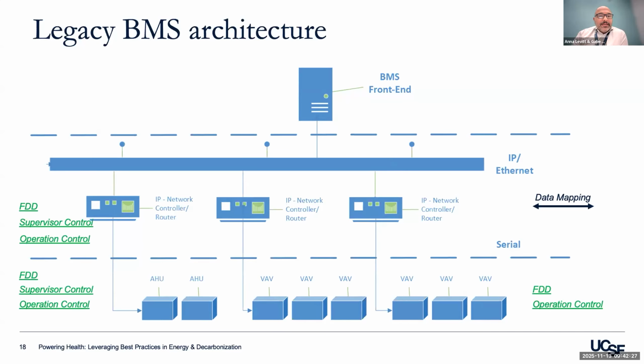Thinking about implementing Guideline 36, if you broke down the different functions or logic that would be deployed, it could be spread across these various controllers. The operation control and fault diagnostic detection could often be in the VAV. In the air handlers, you'd also see the resets running, as well as basic operation control and some fault diagnostic detection. And that programming might also exist in the network controllers as well.